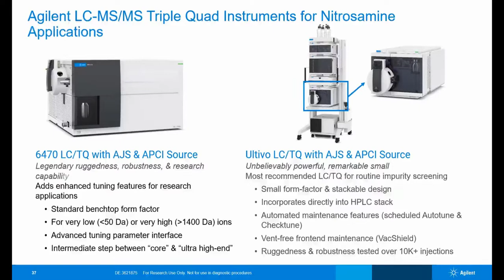Ultivo LC triple quad, on the other hand, is unbelievably powerful and remarkably small. So this is most recommended LC triple quad for routine impurity screening. This is known for its small form factor and stackable design. It incorporates directly into the HPLC stack. It has automated maintenance features like scheduled auto tune and check tune, vent-free front-end maintenance because of the presence of vac shield is available, and it is proven for its ruggedness and robustness with the help of more than 10,000 injections.